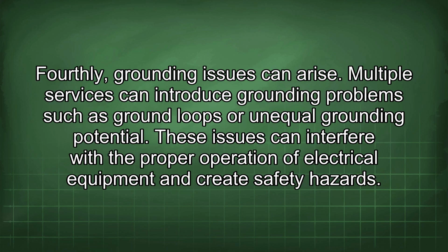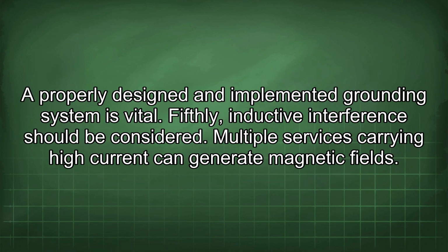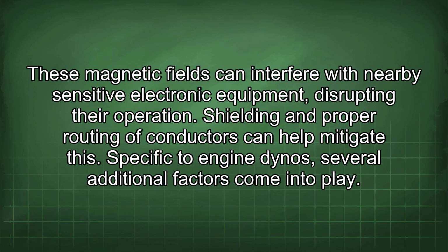Fourthly, grounding issues can arise. Multiple services can introduce grounding problems such as ground loops or unequal grounding potential. These issues can interfere with the proper operation of electrical equipment and create safety hazards. A properly designed and implemented grounding system is vital. Fifthly, inductive interference should be considered. Multiple services carrying high current can generate magnetic fields. These magnetic fields can interfere with nearby sensitive electronic equipment, disrupting their operation. Shielding and proper routing of conductors can help mitigate this.